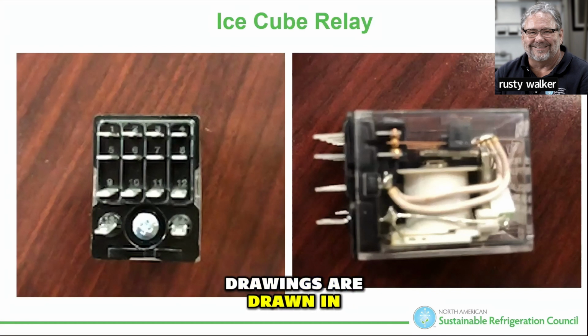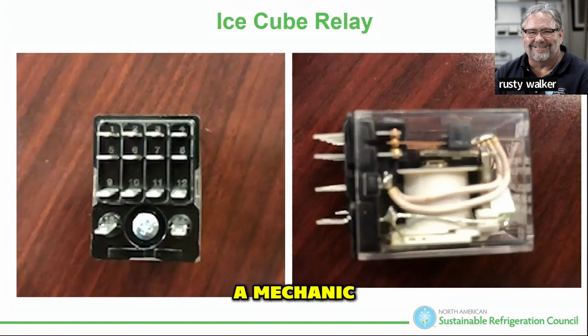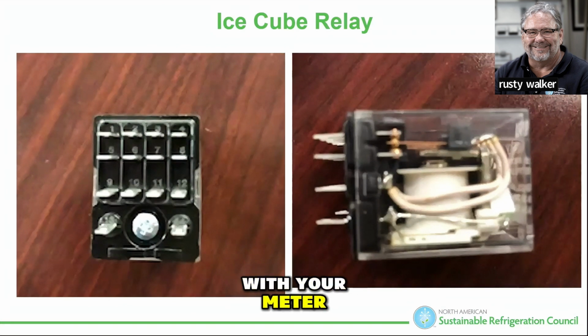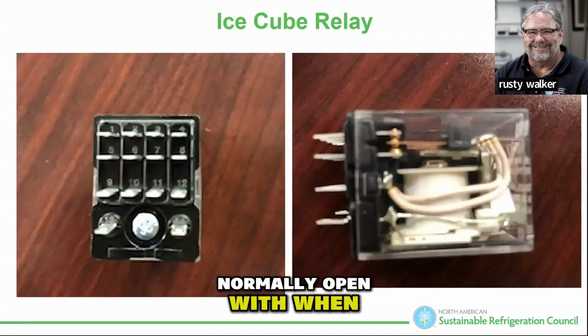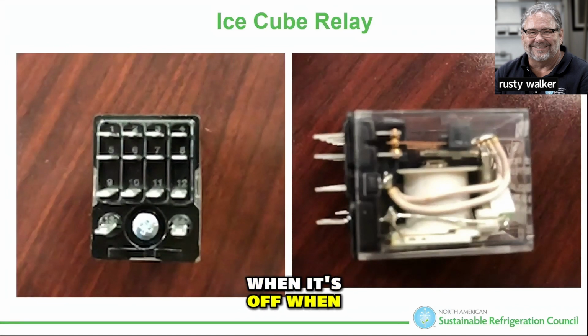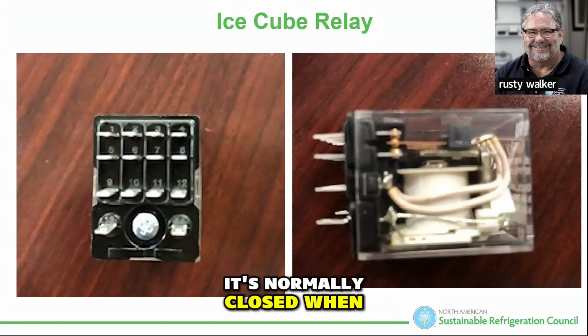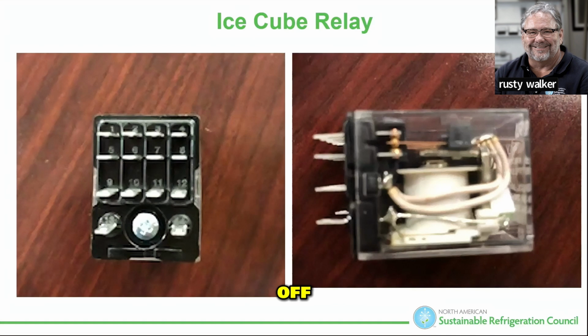Drawings are drawn in the de-energized position - they are off. So as the mechanic or technician, you have to energize the circuit in your head as you're running through it with your meter. Normally open means when it's off, and when I energize that coil, it closes - I turn it on. Normally closed means when the circuit is off, it's closed. To me, that was the epiphany. I wanted to run around the streets naked going, I get it.